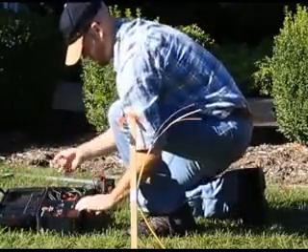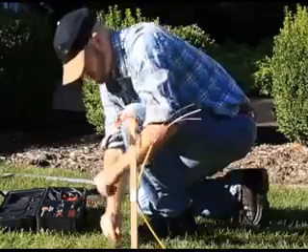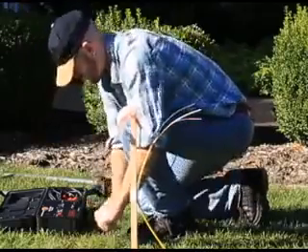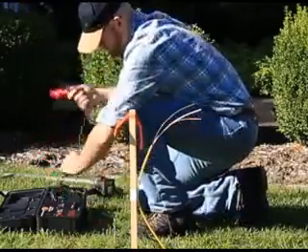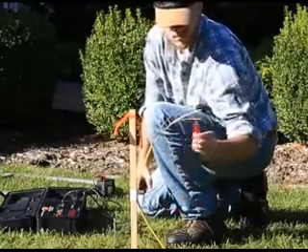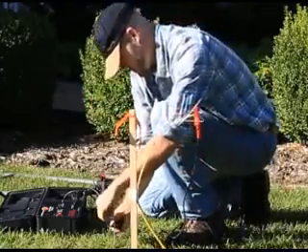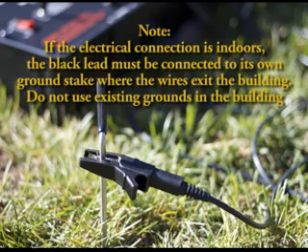At either end of the cable and with the transmitter off, connect the black lead to the ground stake and push the stake into the ground as deeply as possible. Connect the red lead to the cable that is being tested. Note that if the electrical connection is indoors, the black lead must be connected to its own ground stake where the wires exit the building. Do not use existing grounds in the building.